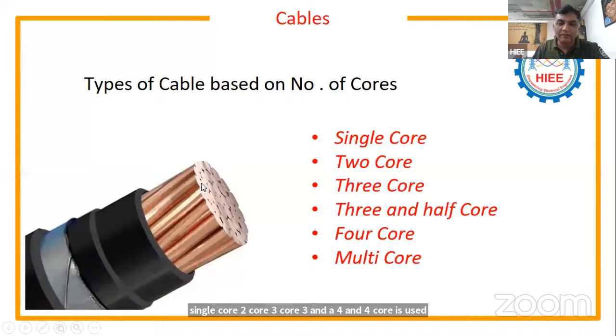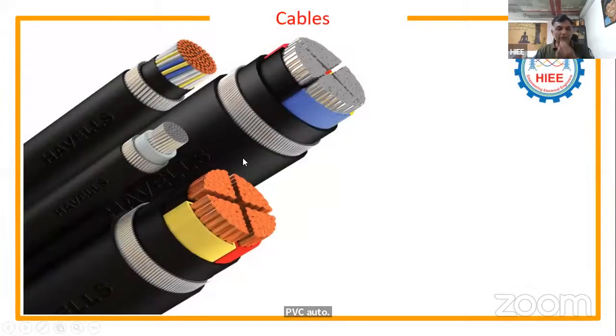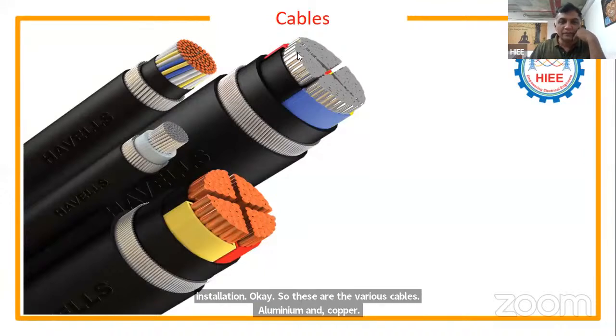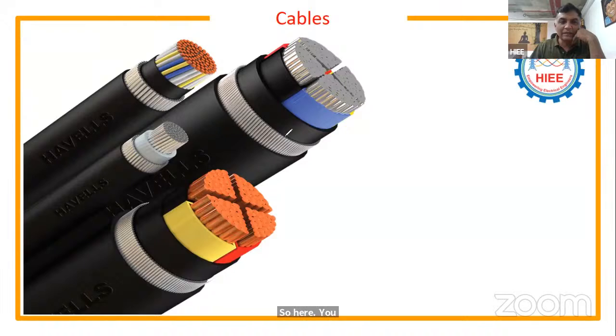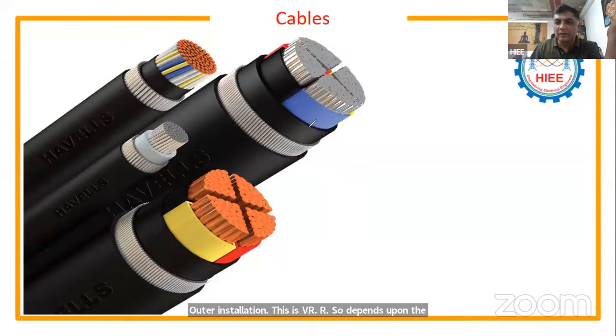Okay, guys, in this picture it is mentioned this is a copper conductor with a PVC insulation and flat armor, again with PVC outer insulation. These are the various cables, aluminum and copper. Here you can see this is an aluminum conductor with XLPE insulation and PVC outer insulation. This is wire armoring and PVC outer insulation. So depending upon the application, we use different types of conductors with different insulating materials.